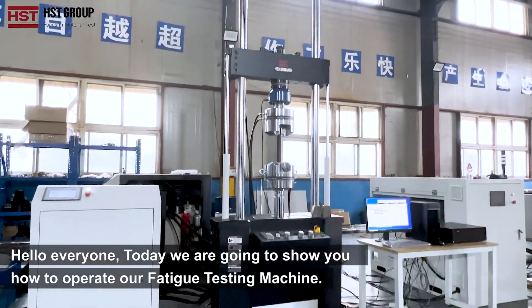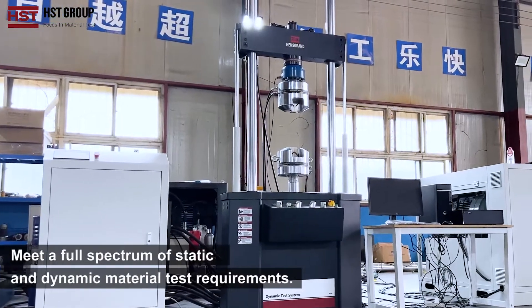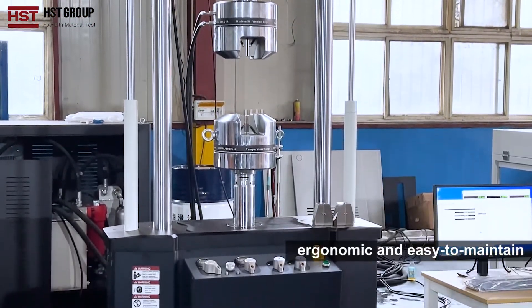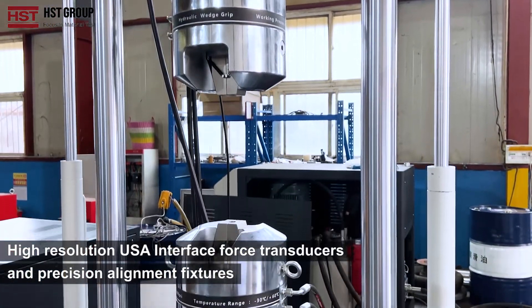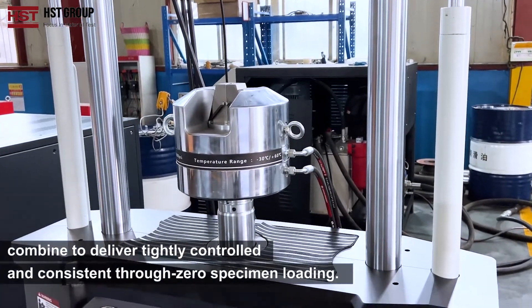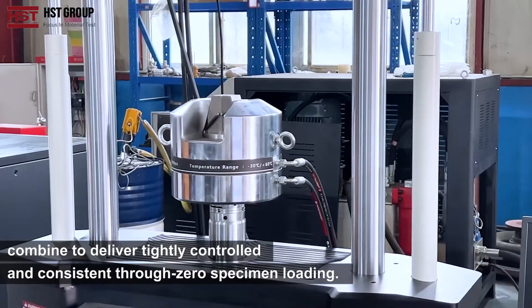Hello everyone, today we are going to show you how to operate our fatigue testing machine, which meets a full spectrum of static and dynamic material testing requirements. The machine is floor standing, load-frame, ergonomic and easy to maintain, with an extremely stiff lightweight crosshead, high resolution USA Interface, and force transducers and precision alignment fixtures that combine to deliver tightly controlled and consistent through-zero specimen loading.